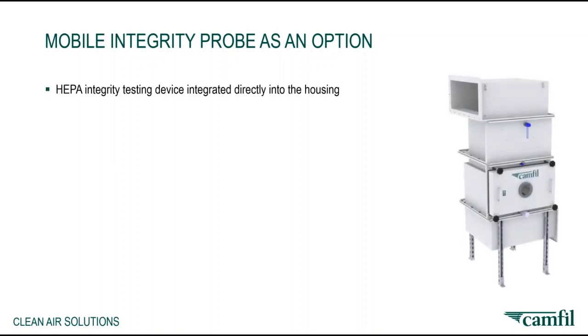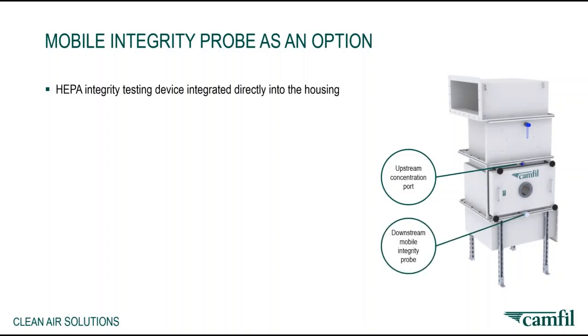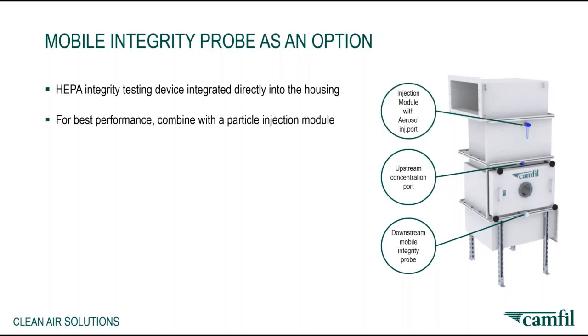Another helpful feature in the validation process of a containment HEPA application is a mobile integrity probe. Usually it's an option. It is a HEPA integrity testing device that gets integrated directly into the housing, and you may recognize it by the access ports, an upstream concentration port and a downstream port to the mobile probe, which is here hidden under the cover. That makes things easier, quicker, cleaner, safer, but for best performances, you should combine it with a particle injection module.